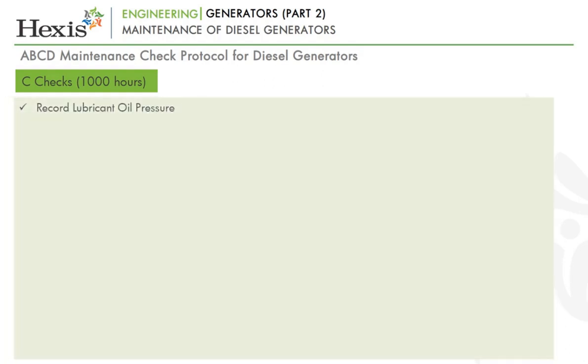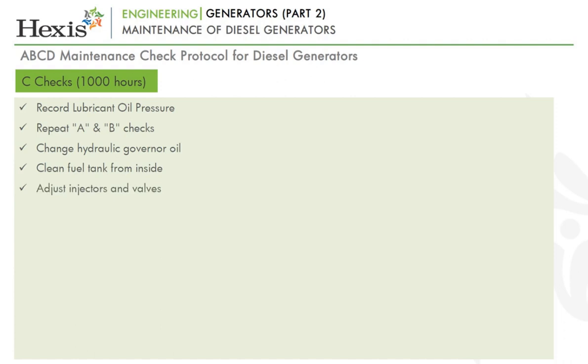The next are the C checks, which are conducted after 1000 hours of DG operation or annually. Record lubricant oil pressure. Repeat A and B checks. Change hydraulic governor oil. Clean fuel tank from inside. Adjust injectors and valves. Replace rocker cover gaskets.